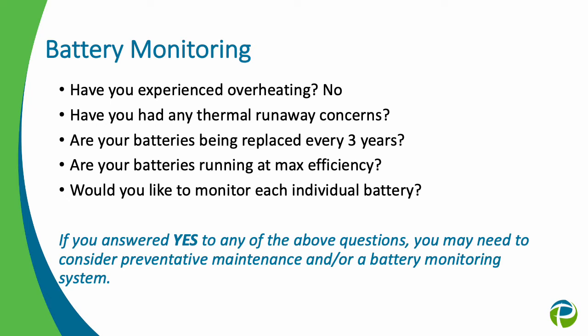So when you're looking at battery monitoring, and when you need to replace, you want to look at: have you experienced overheating? Have you had any thermal runaway concerns? Are your batteries being replaced every 3 years? That's a big one again. Are your batteries running at max efficiency according to your battery monitoring? And also, some people are doing battery monitoring, but not monitoring each individual battery. They might only be monitoring the string. All of our systems that we sell, we can actually get down to each individual battery and monitor that. So it's something to ask yourself: do I want to monitor each individual battery?